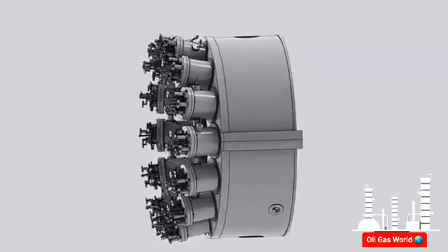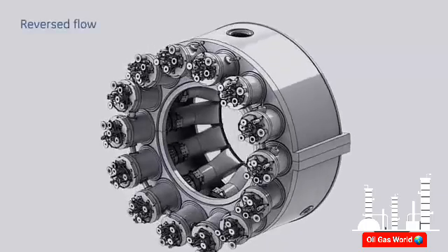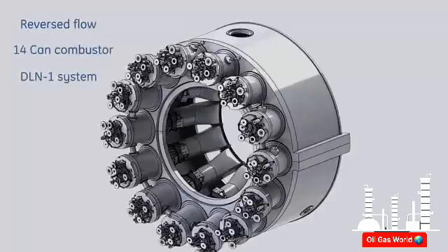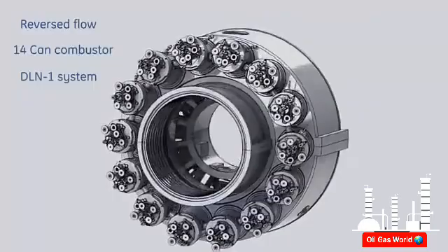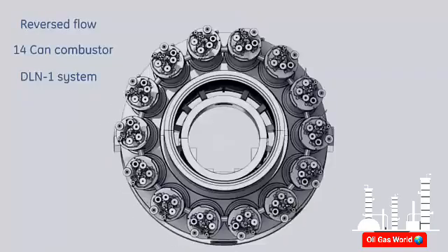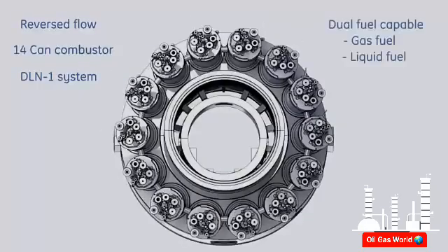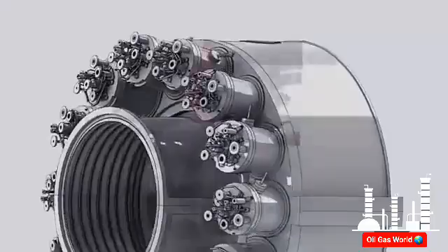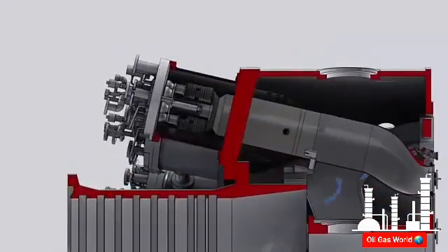The combustion system of this gas turbine is a reverse flow type with 14 DLN1 can-annular combustion chambers arranged around the periphery of the compressor discharge casing. Combustion chambers are numbered counterclockwise as viewed looking downstream, starting from the vertical center line. With dual fuel capability, this turbine burns either gas fuel or liquid fuel. In this section, the pressurized compressor discharge air is directed upstream to enter the combustion zone.